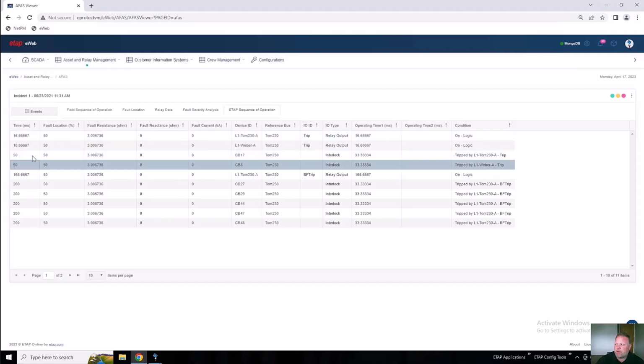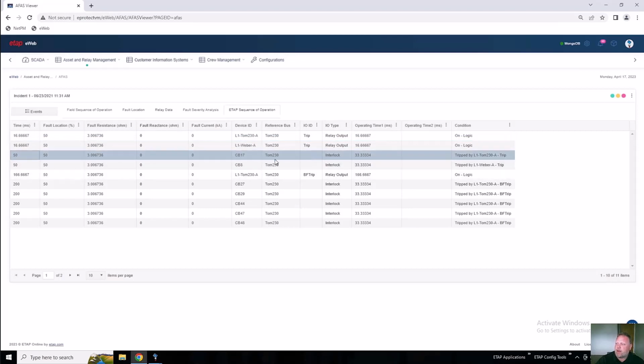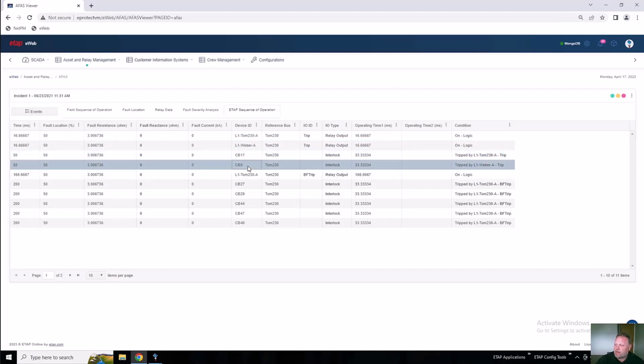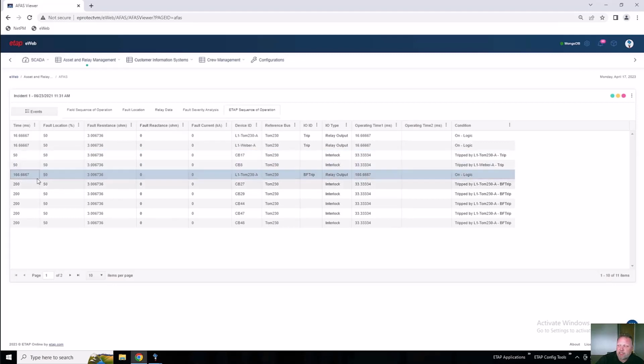At the 50 millisecond mark, we have CB17 and CB8 tripped. And then at the 166 millisecond mark, we have a BF trip as part of the relay protection logic, which causes these other 5 circuit breakers here, 27, 29, 44, 47, and 48, to also trip off due to that bus fault trip protection.